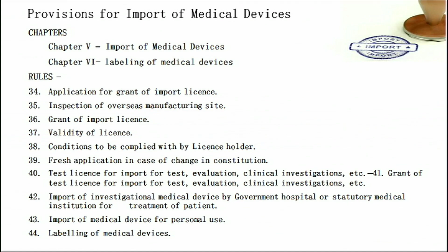And for the labeling of the medical devices imported into the country for marketing, what are the labeling provisions? Chapter 6 of the Medical Device Rules prescribes the labeling requirement. So, these two chapters relate to the import of the medical devices and the labeling requirements for import, and the importer has to comply with the requirements as prescribed in the Medical Device Rules. What are the rules related to import of the medical devices?